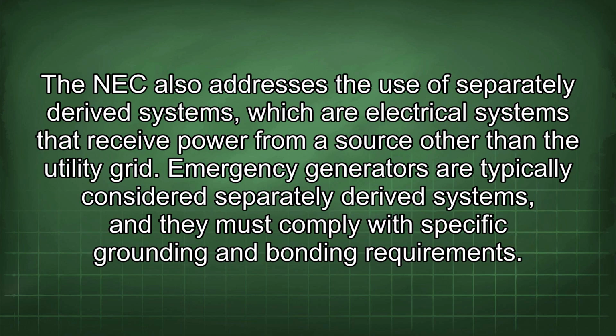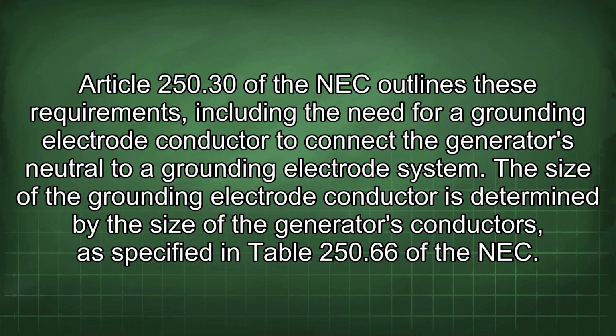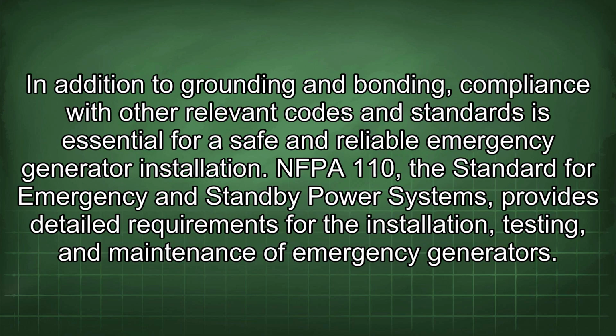The NEC also addresses the use of separately derived systems, which are electrical systems that receive power from a source other than the utility grid. Emergency generators are typically considered separately derived systems, and they must comply with specific grounding and bonding requirements. Article 250.30 of the NEC outlines these requirements, including the need for a grounding electrode conductor to connect the generator's neutral to a grounding electrode system. The size of the grounding electrode conductor is determined by the size of the generator's conductors, as specified in Table 250.66 of the NEC.